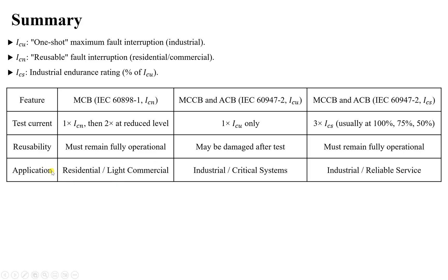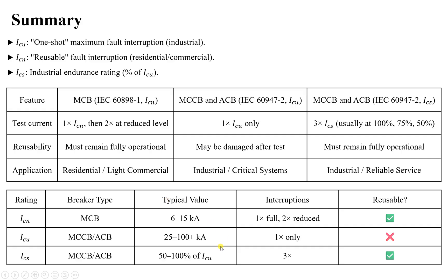Miniature circuit breakers following IEC 60898-1 are used for residential or light commercial applications, while molded case and air circuit breakers following IEC 60947-2 are used industrially. After interrupting, ICN and ICS breakers must remain reusable — the breaker can be operated again after service. However, for ICU, it can interrupt just once and cannot be reused.